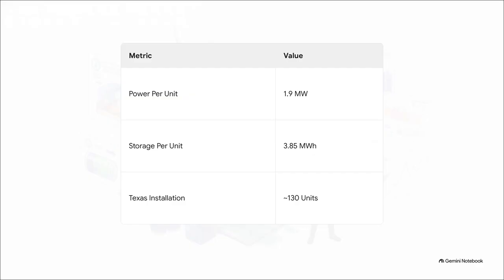When you look at the metrics, it's amazing how modular this system is. A single Megapack unit puts out about 1.9 megawatts of power and holds 3.85 megawatt hours of storage. Because they're completely self-contained, scaling up is just a matter of dropping in more boxes. To hit that massive 500 megawatt hour capacity in Needville, they literally just lined up about 130 of these identical units in neat rows in a Texas field. It's basically like giant, high-tech Lego blocks for the power grid.